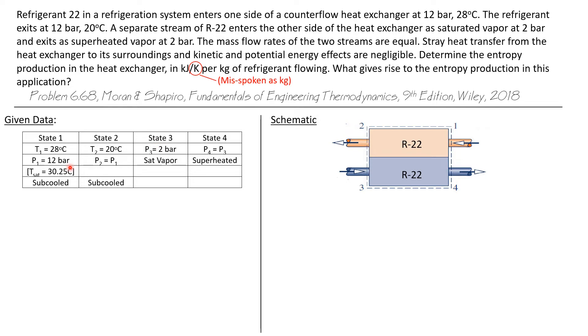Let's see what we know about each of the four states. State one has a temperature of 28 degrees C and a pressure of 12 bar. In the R22 saturation table at 12 bar, the saturation temperature is 30.25 degrees C. This temperature is less than that, therefore state one is a sub-cooled liquid.